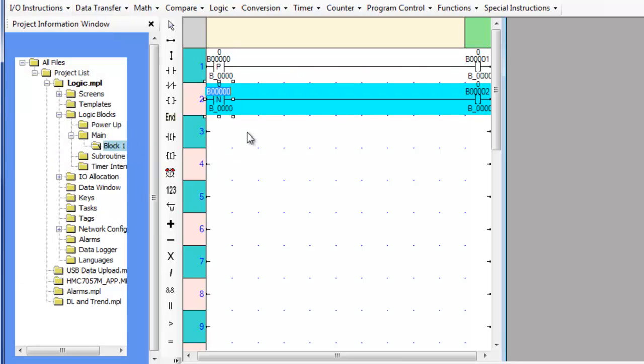The negative pulse contact is a function that will cause a true condition after the contact when the bit is cleared for one scan, if the conditions before the contact are true. The execution time for these instructions is 1.3 microseconds.